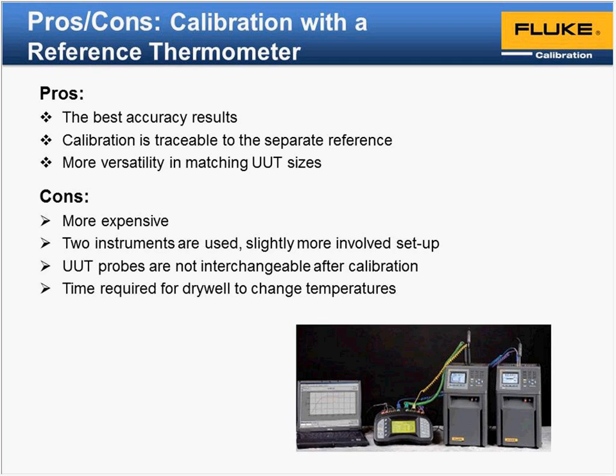Sometimes with these reference thermometers, it gives you some versatility. If you are particularly calibrating just quarter-inch probes or eighth-inch probes, you can get a reference probe that matches ideally to your sensors. That gives you a better fit with the reference. Again, cons: as you add more equipment, your expenses usually go up. And then again, we're using two instruments down the setup as well as a reference. Again, pros, you're typically getting a better calibration.